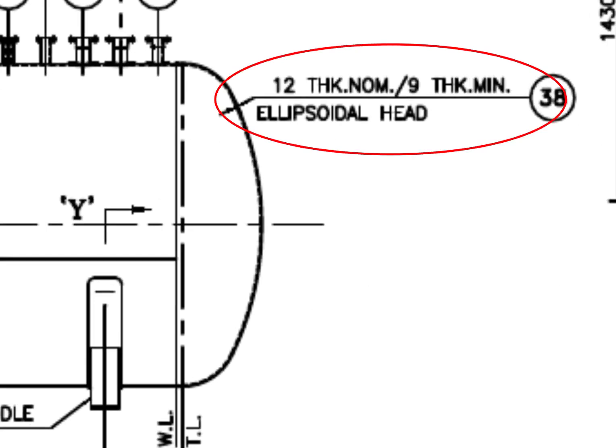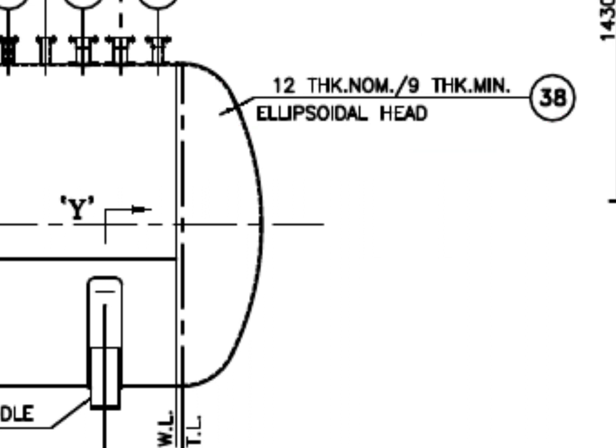See the description. It says the dish end is ellipsoidal, the dish blank thickness is 12 mm and after forming, the minimum thickness shall be 9 mm.